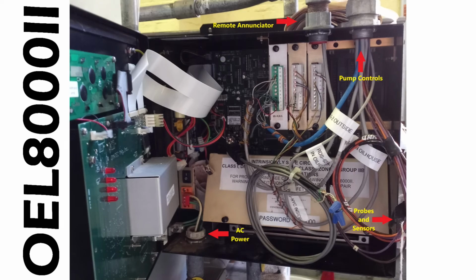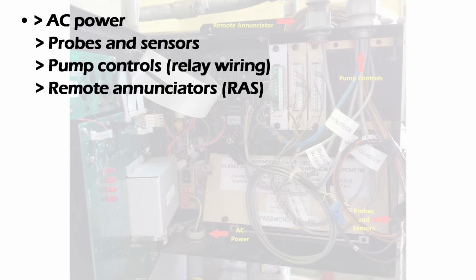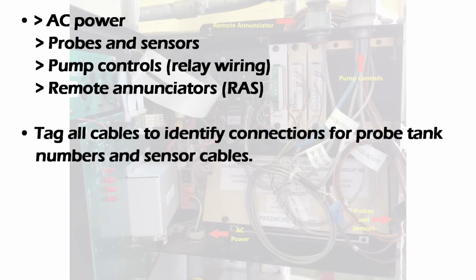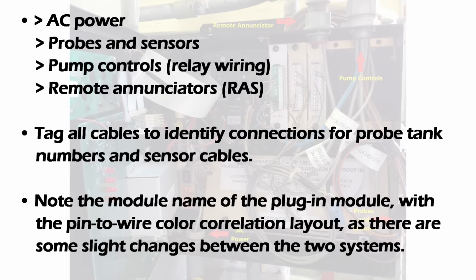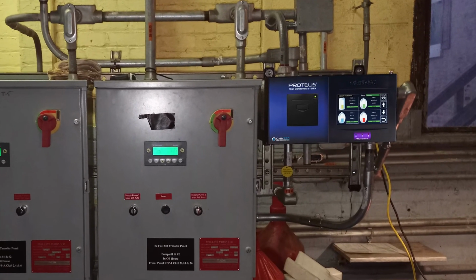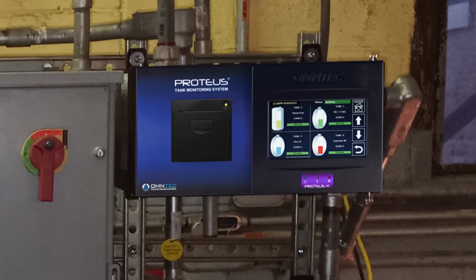If your installation is an upgrade from an OEL 8000II to a Proteus controller, make note of the following cables and their knockouts, as they will need to be rerouted. AC power, probes, sensors, pump controller relay wiring, and remote annunciators. Tag all cables to identify connections for probe tank numbers and sensor cables. Note the module name of the plug-in modules with the pin-to-wire color correlation layout, as there are some slight changes between the two systems. The old probes, sensors, and remote annunciators can be used with the new system.